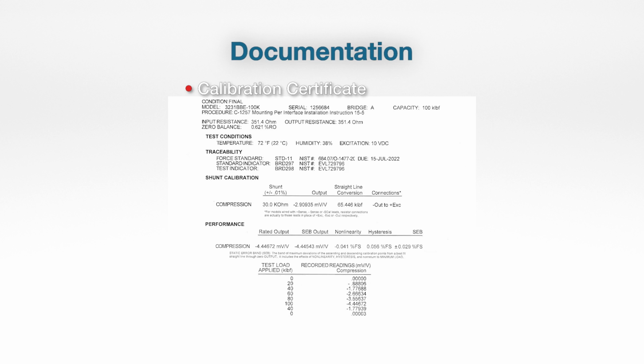So again, the cal cert is a great source for excitation, expected performance, as well as output. Again, you'll see a millivolt per volt output here, whereas if it's an amplified unit, you're probably going to see whatever the high-level output is on there.